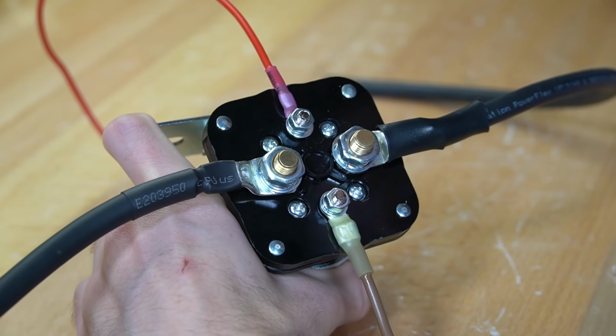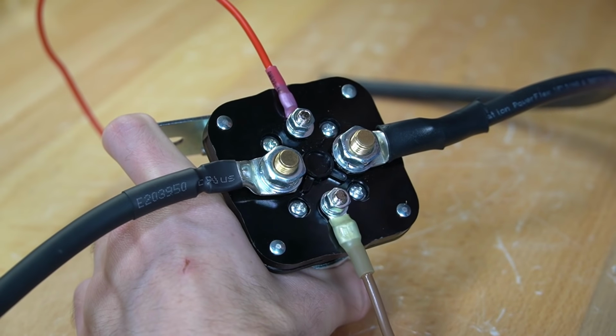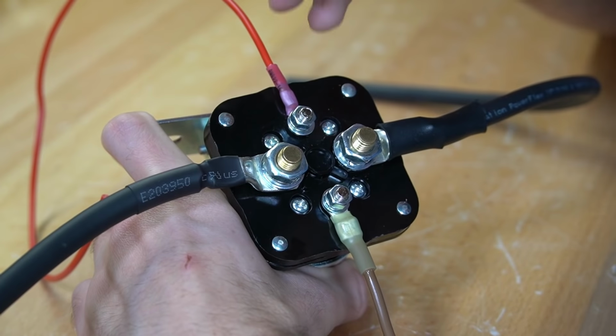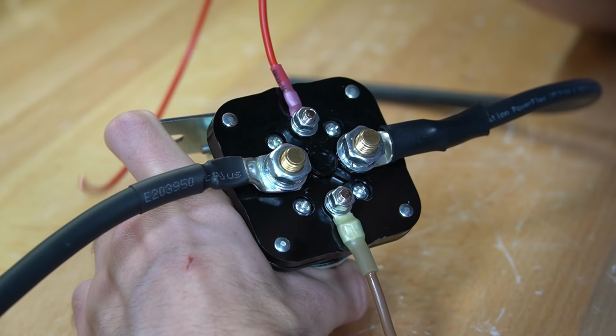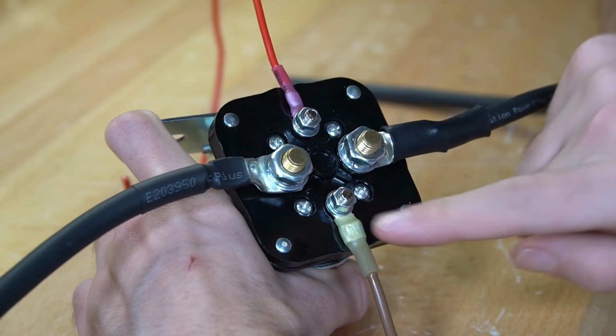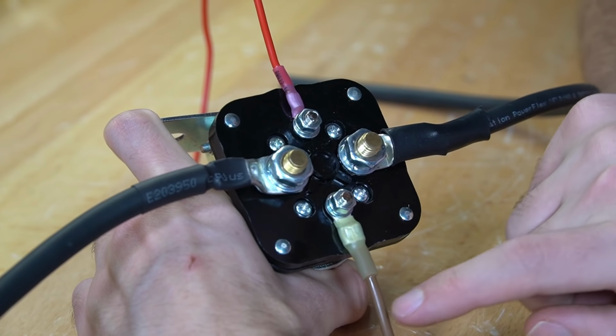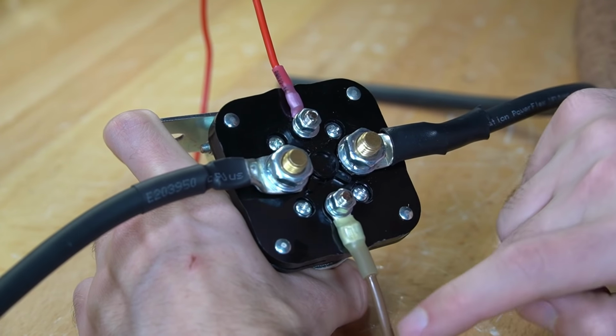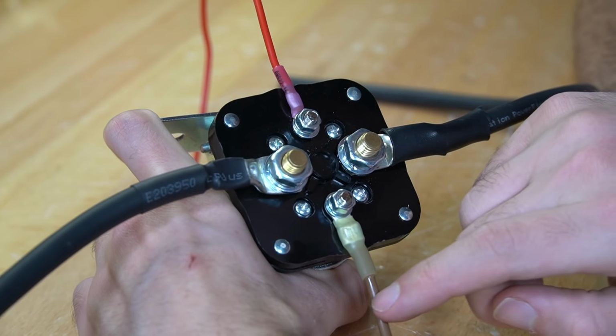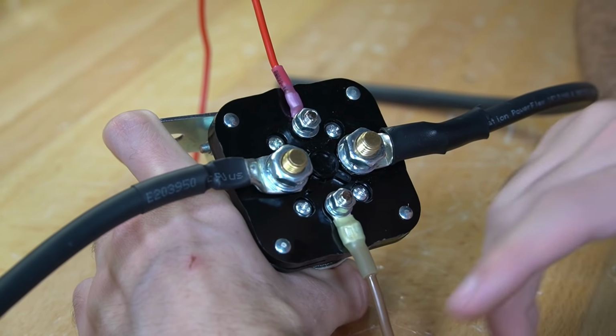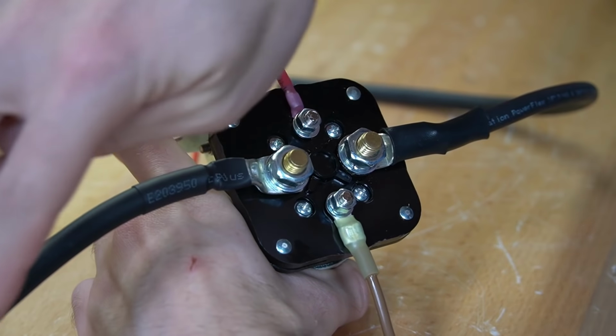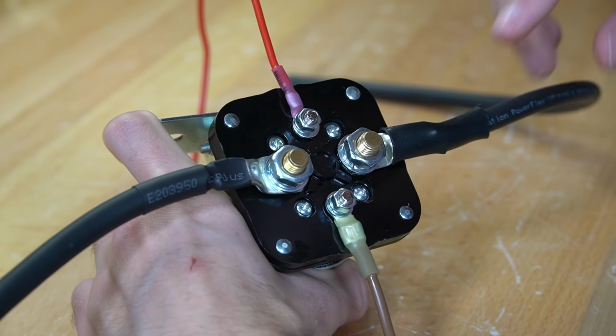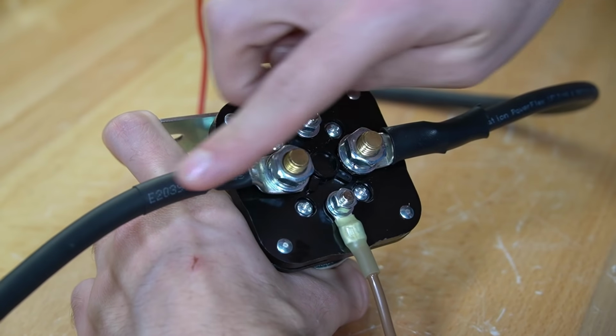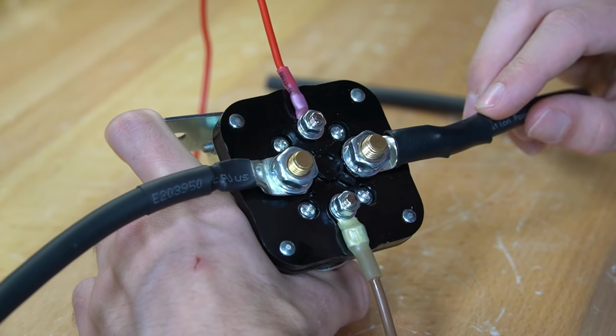Now let's give an example of how you would wire this relay into a solar power system. First, we have two terminals and they need 12 volts. This one's going to go to the main positive terminal of your battery. And this one will go to the BMS output, or the P negative. Whatever your BMS connects to loads for low voltage disconnect, you want to connect this wire to that. Then these two large terminals, these large wires, will go between your inverter and your battery. This could be the inverter negative cable, or it could be the inverter positive cable. It does not matter. Something else that doesn't matter is the polarity of these two terminals.